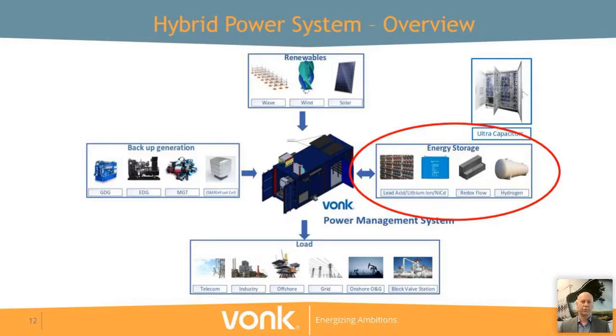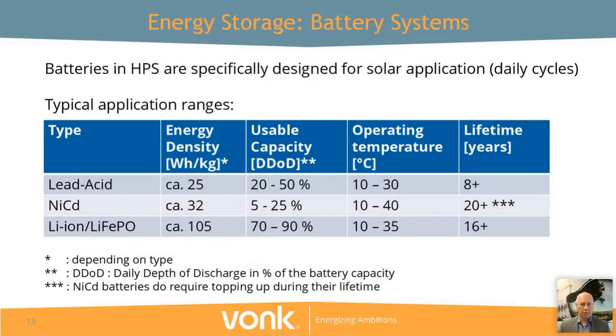There are different ways for energy storage, but batteries are most commonly used. Batteries is just one term, but there are very different types on the market, and it really depends on the situation which option would be most preferable. We always try to optimize our battery system to the specific situation, and it's important to know the operating temperature and the daily depth of discharge possible for each battery type.